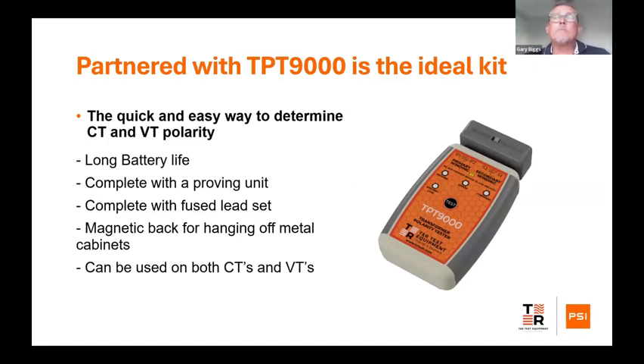And then, partnered with our relay test set, we have a little CT polarity test set. This is a very light, simple tester, and it's an ideal commissioning tool. If you're doing an upgrade to a substation and you're fitting new equipment, this is a quick way of telling which way round the CT has to go. The unit's very, very easy to use. It has a magnetic back, so we can just put it onto the cabinet while we're testing. The unit can be used for both CTs and VTs. So it's a very handy little test set, giving you quite a lot of tests out of a little 9-volt battery.